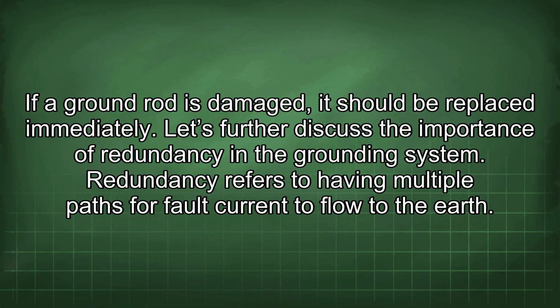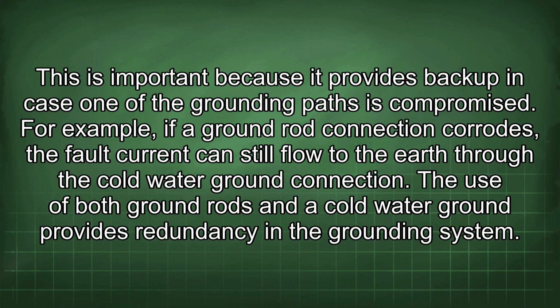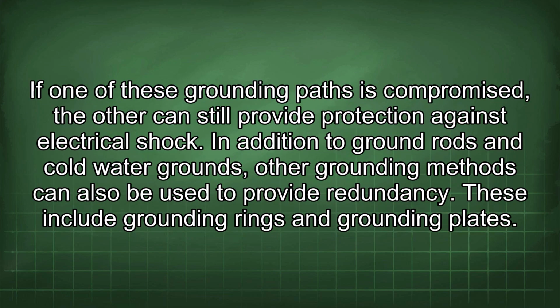Let's further discuss the importance of redundancy in the grounding system. Redundancy refers to having multiple paths for fault current to flow to the earth. This is important because it provides backup in case one of the grounding paths is compromised. For example, if a ground rod connection corrodes, the fault current can still flow to the earth through the cold water ground connection. The use of both ground rods and a cold water ground provides redundancy in the grounding system. If one of these grounding paths is compromised, the other can still provide protection against electrical shock.